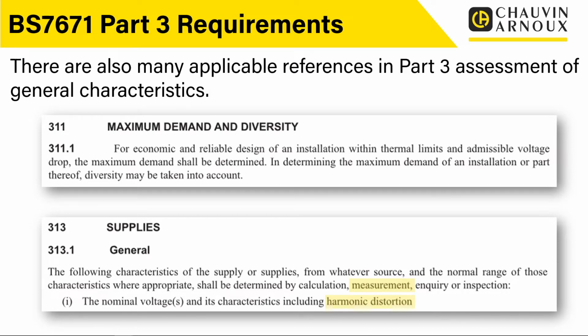Now also 313, supplies, actually talks about the characteristics of the available supply or supplies, and it says the following characteristics of the supply or supplies from whatever source, and the normal range of those characteristics where appropriate, shall be determined by calculation, measurement, inquiry or inspection. And the first one on there, it says the nominal voltage and its characteristics including harmonic distortion. So if we are going to be looking at the supply in there, it does say that we actually need to know not just what the nominal voltage is, but any characteristics of that, so the harmonic distortion. So again, we really need to be able to measure that and actually understand, is there actually any problem with the incoming supply that's going to introduce harmonics and harmonic distortion into our installation that we need to allow for.